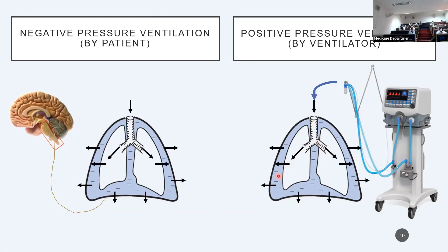In stark contrast to this, in positive pressure ventilation by a ventilator, first the ventilator increases the pressure inside the tubing. So there's a higher pressure outside compared to inside. Thus, air moves from higher pressure to lower pressure inside the lungs. This positive pressure is transmitted to the intrapleural space, subsequently leading to downward motion of the diaphragm and outward motion of the chest wall, which is visible as a chest rise in these patients. During expiration, the pressure in the circuit reduces. Thus, air moves from the outer higher pressure to the lower pressure. With the movement of air, there is a decrease in the intrapleural pressure, and the diaphragm moves up and the chest wall falls, the opposite of the chest rise.